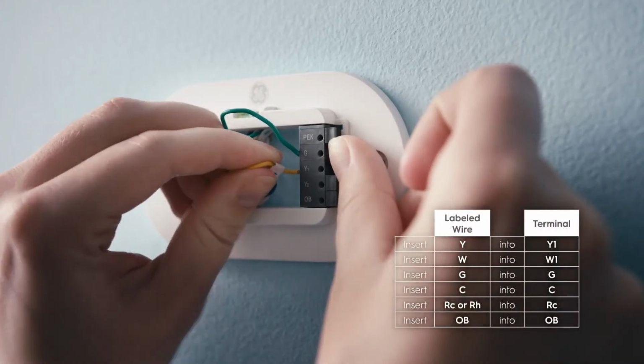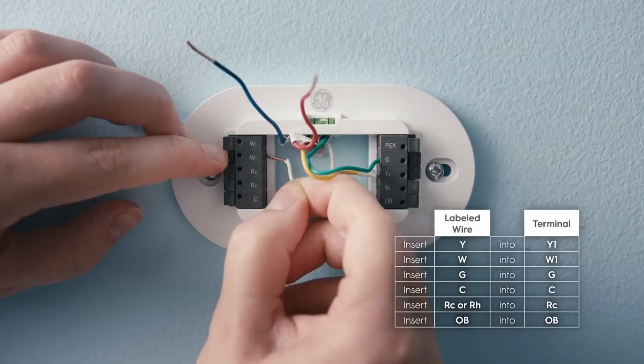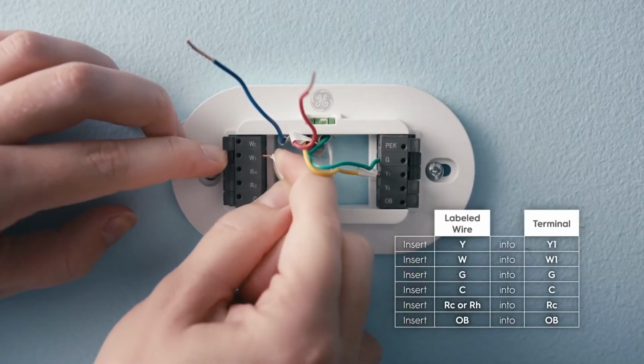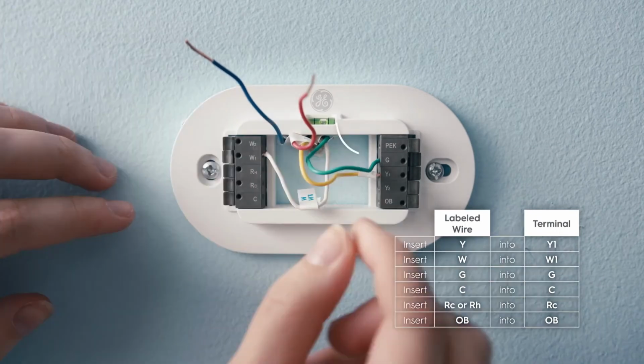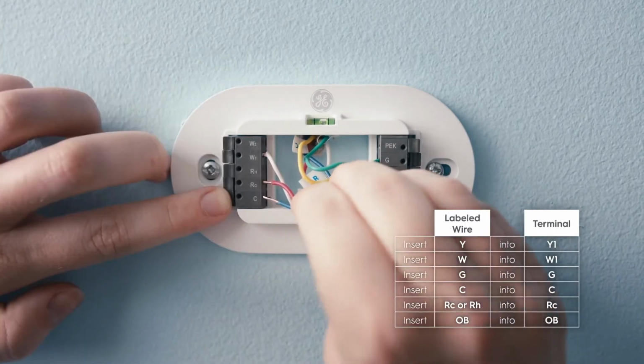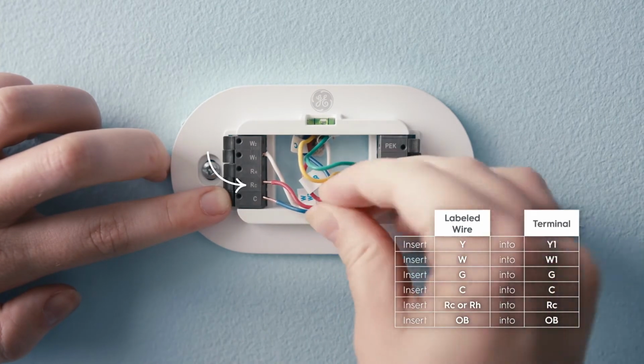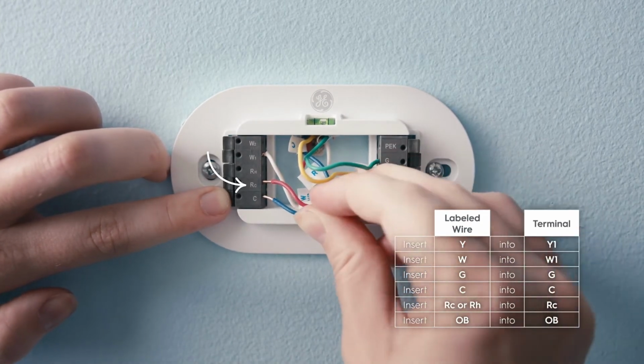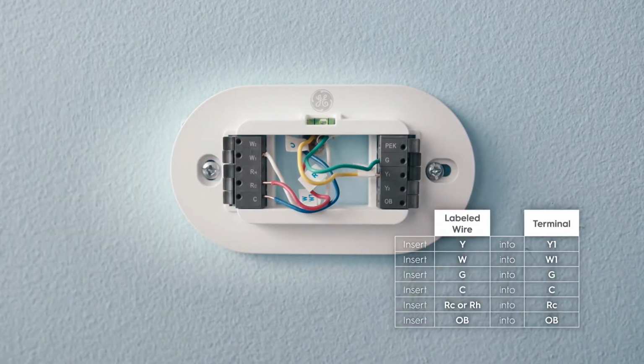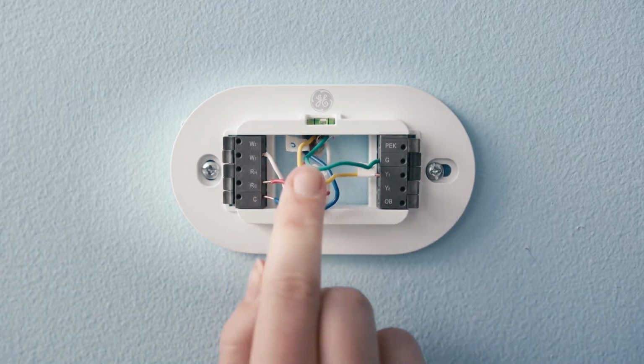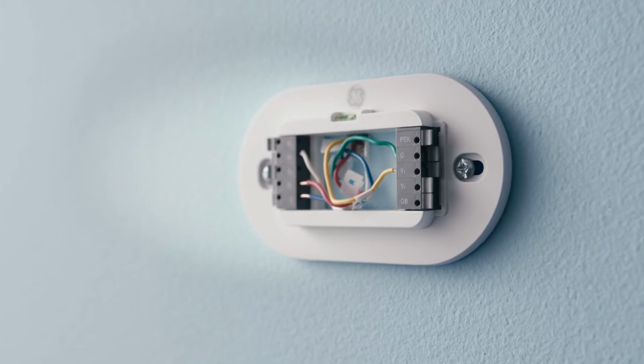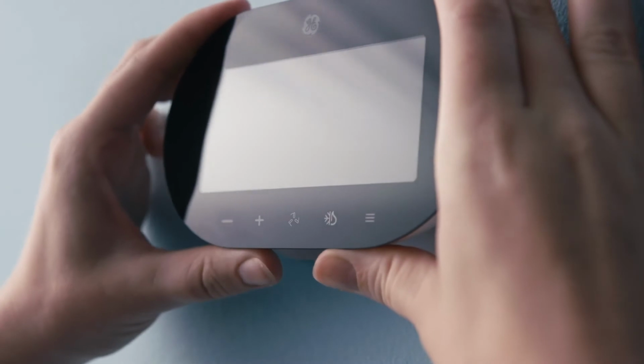Wire Y or Y1 should go to terminal Y1. Wire W or W1 should go to terminal W1. Wire G to terminal G, wire C to terminal C, and wire RC or RH to terminal RC. For heat pumps, connect wire OB to the OB terminal. Insert any remaining wires into their corresponding terminals on the backplate. Tuck any excess wire into the wall. Step 5. Mount your new smart thermostat onto the backplate. The thermostat control buttons should be along the bottom.